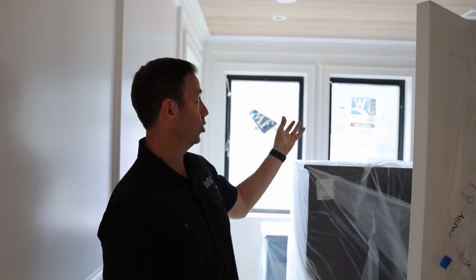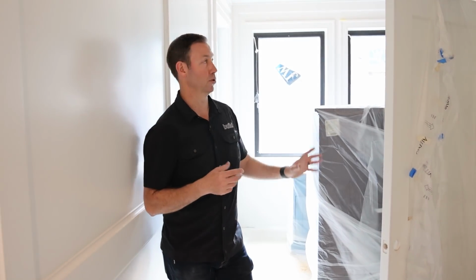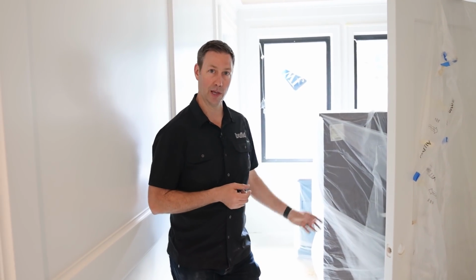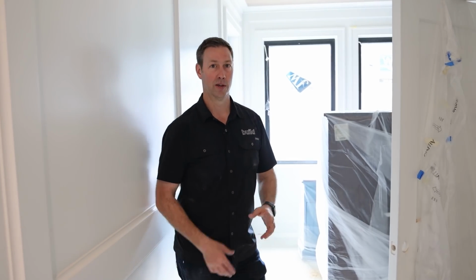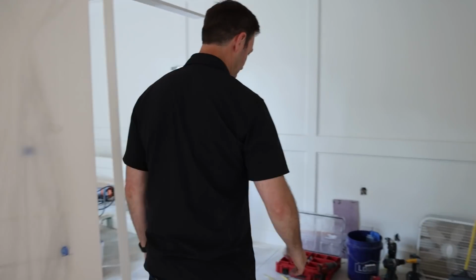And when we finish commissioning the system, we're going to put a flow hood on there and verify that we're within 10% of the intended number. So master bedroom's probably what, 130 CFM, let's say, out of that. We're going to make sure that we're within 117 to 140 something CFM to make sure that that's really working right.